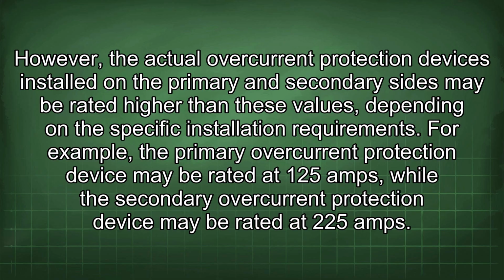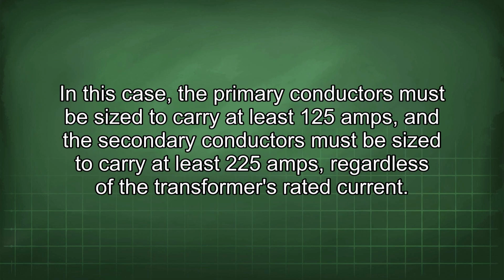However, the actual overcurrent protection devices installed on the primary and secondary sides may be rated higher than these values, depending on the specific installation requirements. For example, the primary overcurrent protection device may be rated at 125 amps, while the secondary overcurrent protection device may be rated at 225 amps. In this case, the primary conductors must be sized to carry at least 125 amps, and the secondary conductors must be sized to carry at least 225 amps, regardless of the transformer's rated current.